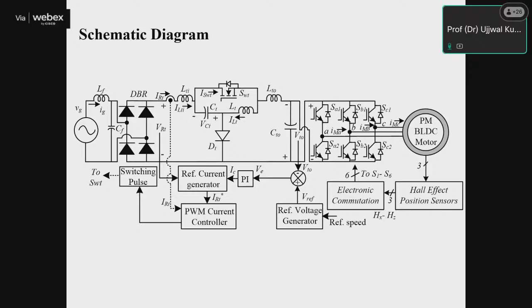Then the DSP controller will execute the control algorithm, and it must be able to execute it before 40 microseconds - maybe in 36, 37, or 38 microseconds. If it fails to execute the algorithm within 40 microseconds, it will start malfunctioning, and in that case you'd have to increase the sampling time of the converter.